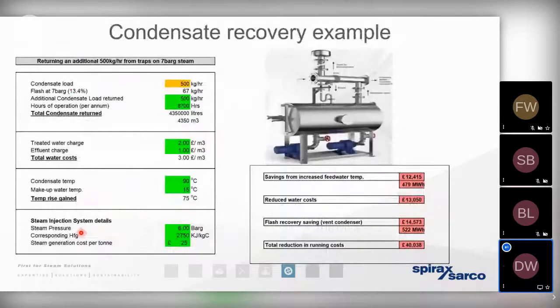So whenever we're talking about recovering condensate, or understanding the financial benefits of engineering a solution to minimize flash steam and maximize condensate recovery, we need to know the condensate load. We need to have an understanding of the amount of energy that's present in that condensate. We need to know how much our raw water costs, what our effluent costs are. We need to have an understanding of what our chemical costs are. And it's only then that we can start to appreciate the benefit of engineering a solution that will increase the rate of condensate return and minimize the amount of flash that is expelled to atmosphere.